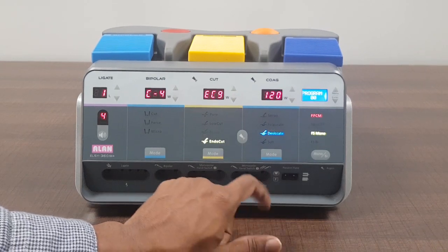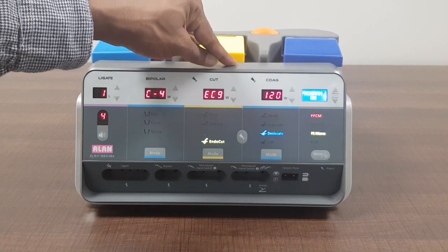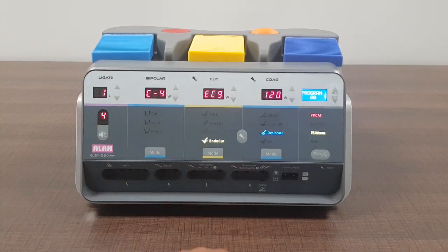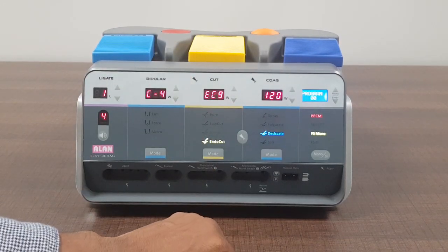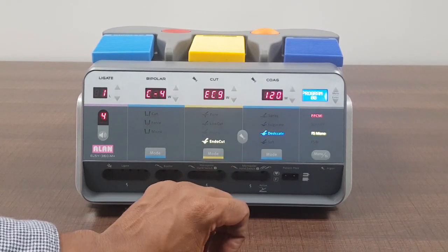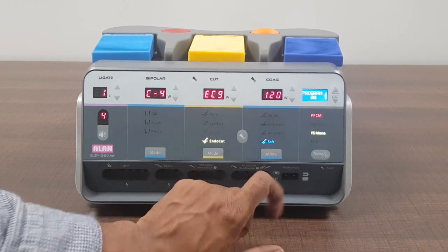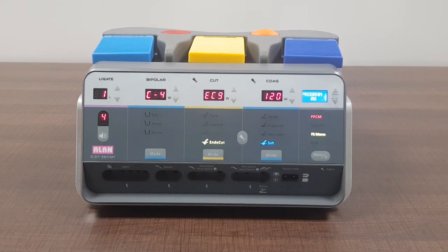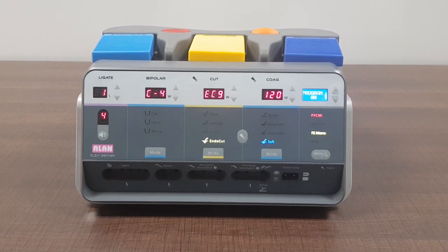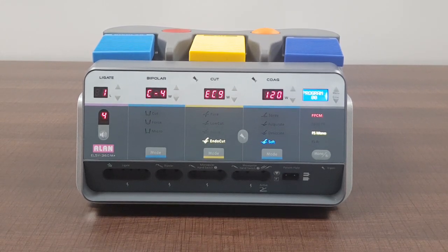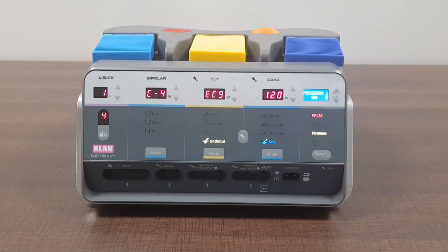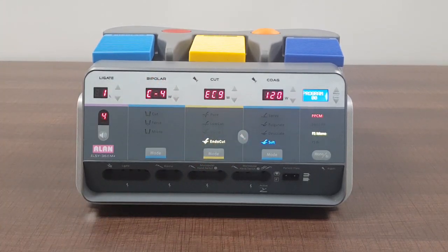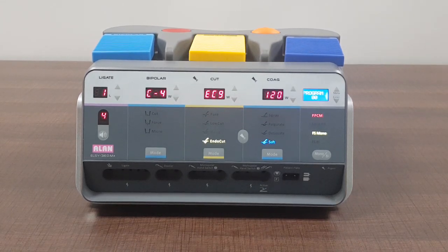Then comes desiccate. In desiccate this is a contact coagulation. Contact coagulation means you can touch the electrode to the tissue and press desiccate. The maximum is 120 watts. Even this coagulation, desiccate is a little deeper and this is most commonly used, desiccation in human and the same thing can be used in vets as well. Next is soft. Soft is specifically meant for those tissues wherever the tissues are very fragile, very soft and the resistance is very small. These kind of things are basically used in neurosurgery as well. But if you feel that this tissue is quite soft and using any other feature can actually create carbonization or charring, then I would suggest take a soft coagulation. This one coagulates the tissue but the charring is less with less intensity. The maximum is 120 watts.